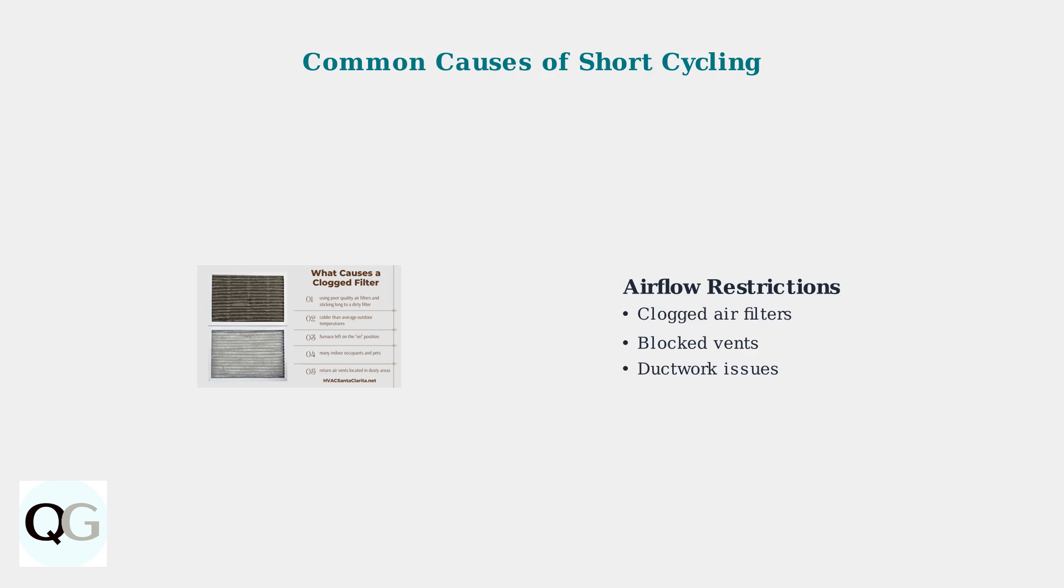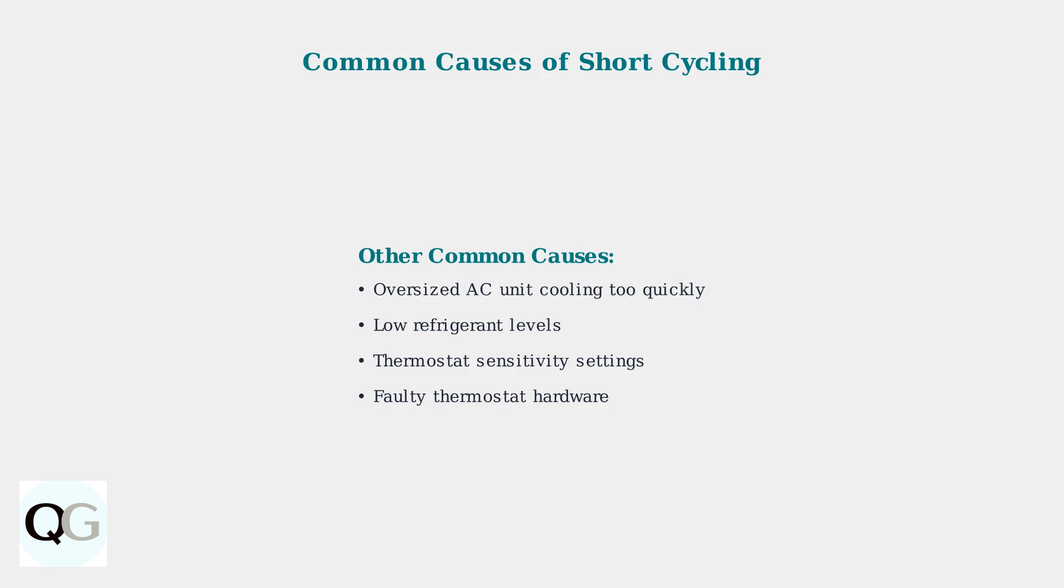This creates the short cycling pattern as the system struggles to maintain proper operation. Additional causes include an oversized air conditioning unit that cools your space too quickly, low refrigerant levels, overly sensitive thermostat settings, or hardware problems with the thermostat itself.